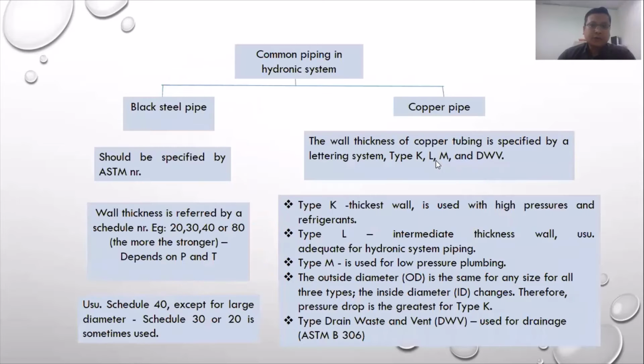Okay, we go based on the material system. We separate by the black steel pipe and the copper pipe. So where the copper pipe will be used, and where the black steel pipe will be implemented in the HVAC system. In the HVAC system, for the black steel pipe, we will consider schedules from 20 until 80. Schedule itself refers to the wall thickness of the pipe. So if you want a higher thickness, the schedule number should be higher.